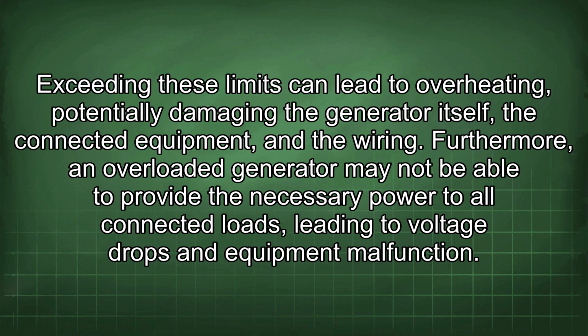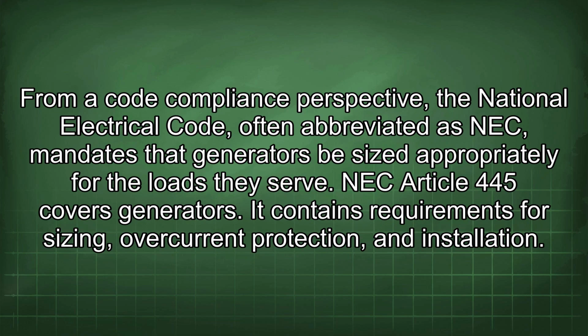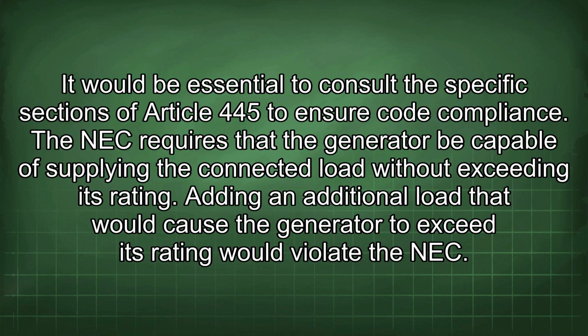Furthermore, an overloaded generator may not be able to provide the necessary power to all connected loads, leading to voltage drops and equipment malfunction. From a code compliance perspective, the National Electrical Code, often abbreviated as NEC, mandates that generators be sized appropriately for the loads they serve. NEC Article 445 covers generators. It contains requirements for sizing, overcurrent protection, and installation. It would be essential to consult the specific sections of Article 445 to ensure code compliance.